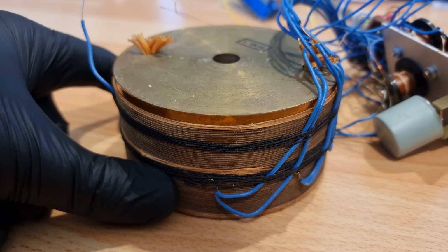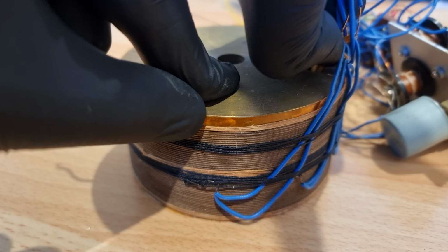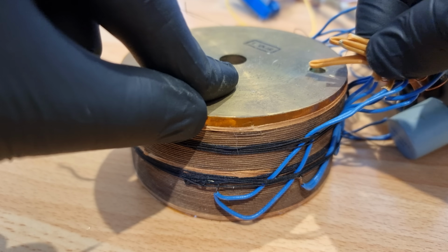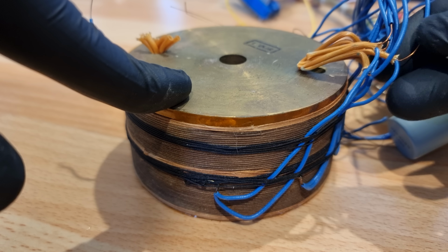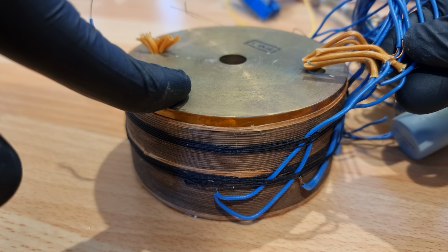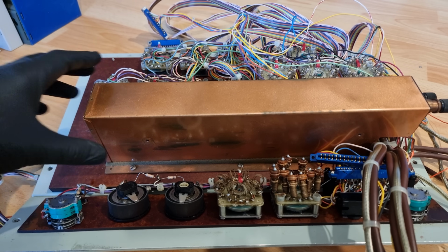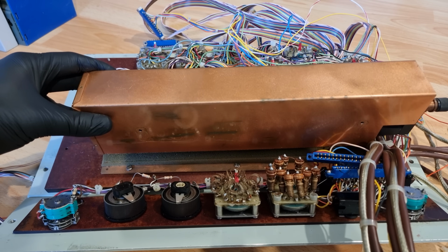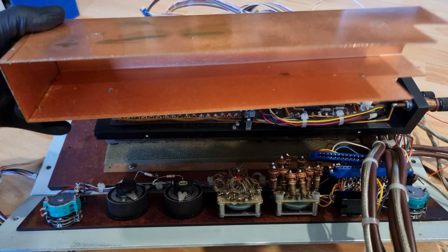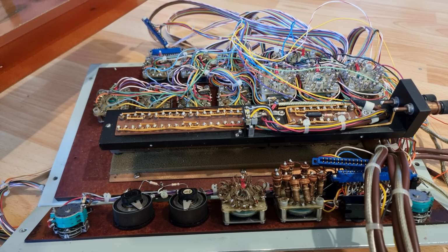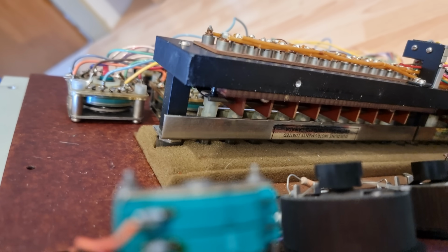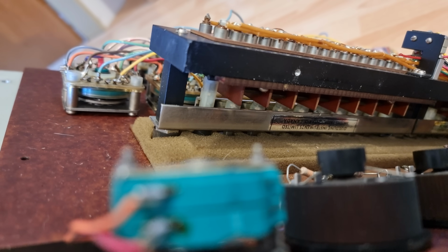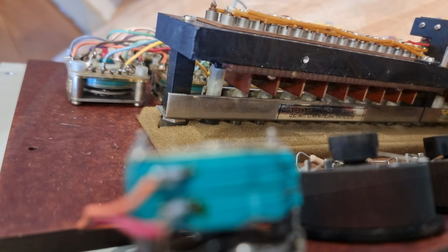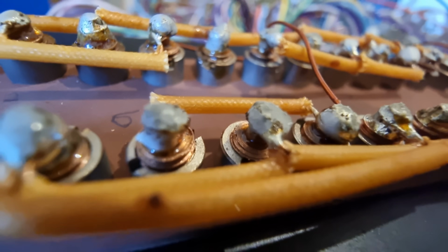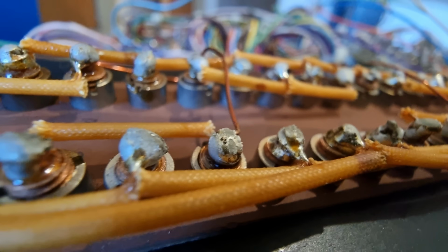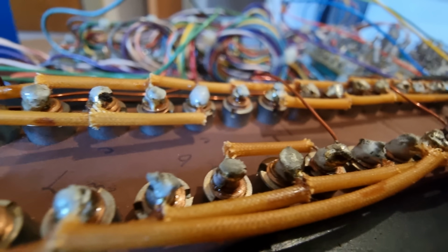I also love the way they are burying the solder joints between resistive elements and interconnecting wires deep within the brass block to ensure that those two are always at equal temperatures to avoid thermocouple effects. The user interface has another luxurious copper can, under which the range and function push buttons are hidden. It seems like at this point in the circuit thermal EMFs do matter, because there's foam insulation to where an operator might rest his hands. And the solder in here looks different to everywhere else in the system, maybe a specialized alloy? Yet another application for delicious cadmium maybe.